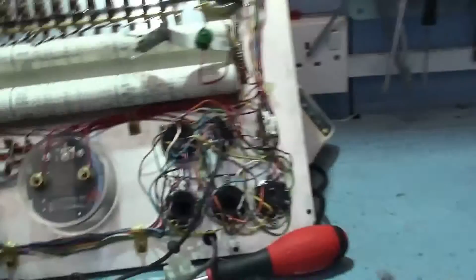Actually, that was quite a good invention that Avo used, the Avo 8 particularly, but all the models, I think they perfected it in the Avo 8. It was a travel limiter, and if the meter hit the end stop too hard, it would actually trip in the mechanism of the meter, and actually release the voltage to the meter. So that was quite a good protection.